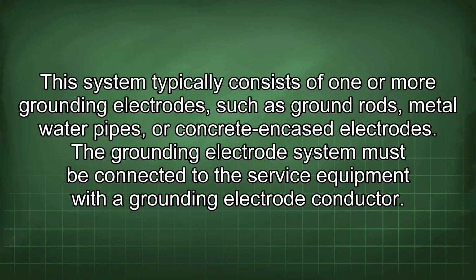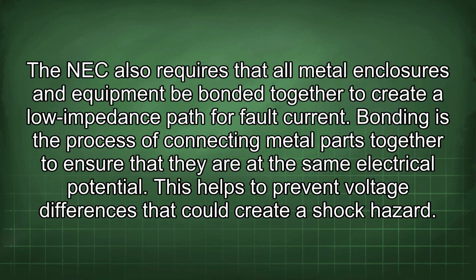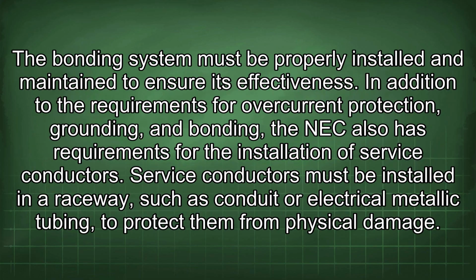The grounding electrode system must be connected to the service equipment with a grounding electrode conductor. The NEC also requires that all metal enclosures and equipment be bonded together to create a low impedance path for fault current. Bonding is the process of connecting metal parts together to ensure that they are at the same electrical potential. This helps to prevent voltage differences that could create a shock hazard. The bonding system must be properly installed and maintained to ensure its effectiveness.